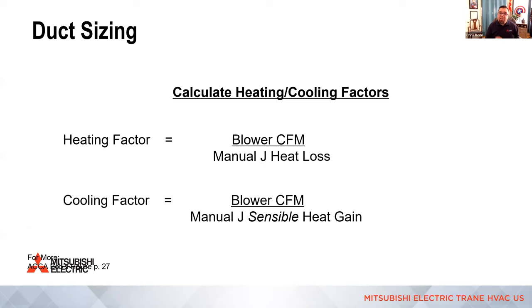So this is what the worksheet looks like on the top side. This is how we calculate the heating and cooling factors. We need to know the blower CFM in heating divided by the Manual J total heat loss for that area or room, right? So with a low static air handler, this would be one or two rooms. Of course, if you're doing a whole floor, it would be the Manual J heat loss for that whole floor in order to then associate the correct volume of air to each room.